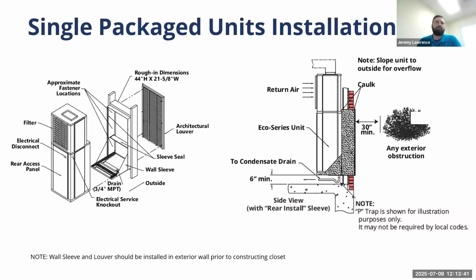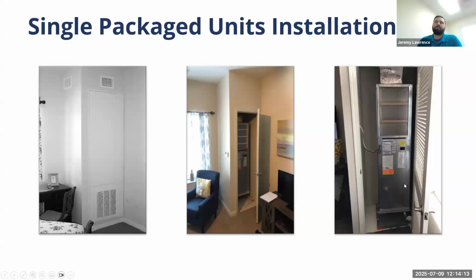But even in northern installations here in Canada, we rarely use them. Never seems to be a problem. Return air is pulled straight from the room. There is a duct kit if you wanted to duct the return air straight off the closet door. However, it is preferred that the return air is left open with the filter accessible. One, because the filter is accessible, but also because of how it fits into this closet, the closet space becomes part of the return air and avoids any water or condensate building up on the exterior of the unit in cold operating temperatures. So that's a great benefit as well.